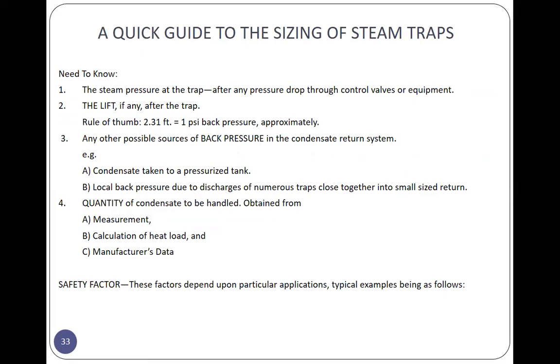Need to know: 1, the steam pressure at the trap after any pressure drop through control valves or equipment. 2, the lift, if any, after the trap. Rule of thumb, 2.31 feet is equal to 1 PSI back pressure approximately. 3, any other possible sources of back pressure in the condensate return system. A, condensate taken to a pressurized tank. B, local back pressure due to discharges of numerous traps close together into small size return. Number 4, the quantity of condensate to be handled.